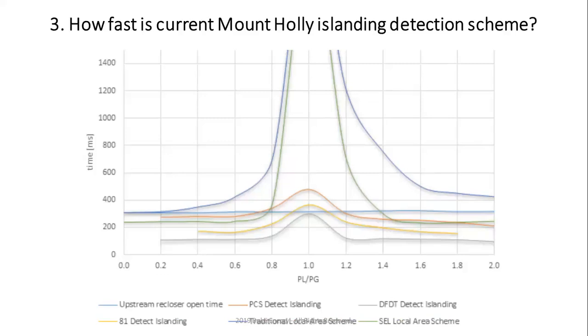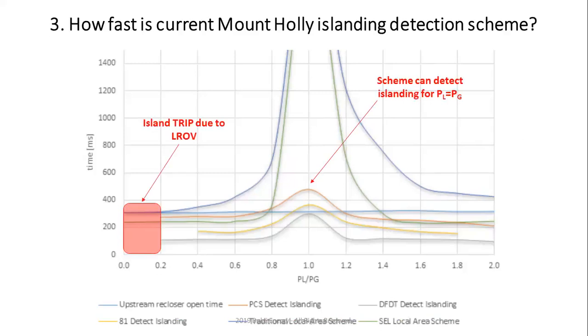However, if you ever try to test that, if your scheme is too fast, which ours was, and we try to detect it on the change of the 52A switch, that would never work, because the system changes much faster than the switch opens. So these numbers right here on the left side are actually much faster in real life, but we had to initiate the event recording by pushing the button on the front of the relay to go open, which means that there's still some time after that. So even at these speeds it's really fast, but in real life it's actually even faster, right? So 2 things: the scheme can detect islanding for PL over PG, and you can clearly see there are no non-detection zones. And second of all, if you see on this particular screen that there is a response time between 0.0 and 0.2 PL over PG, that means that we have a whole lot of generation and not very much load.